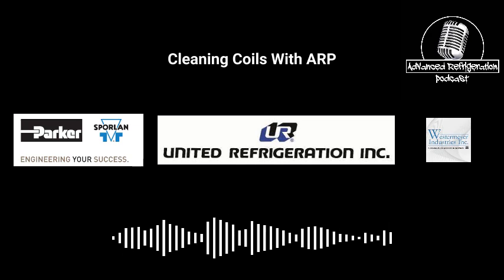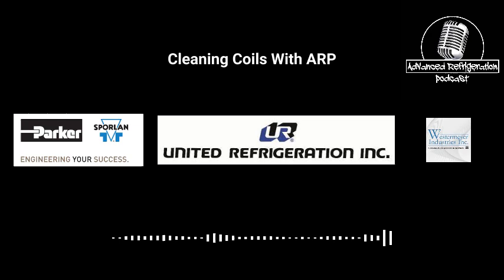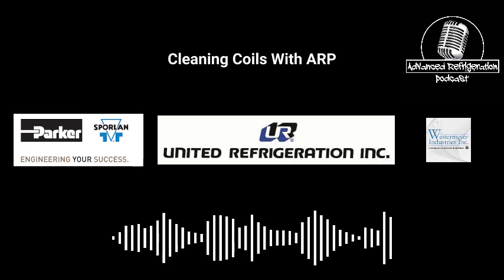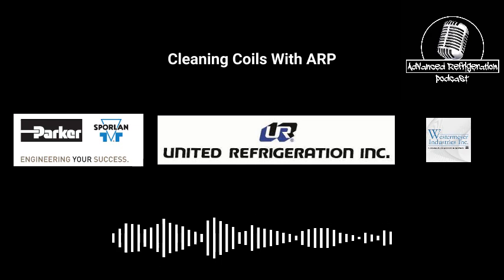If you look at the bottom of it and it looks clean and you're blowing air out the sides and you're over motors, you're impacted. Your condenser is blocked up. It's not that it has non-condensables or anything like that. If that air isn't blowing straight up, that condenser is impacted with dirt.